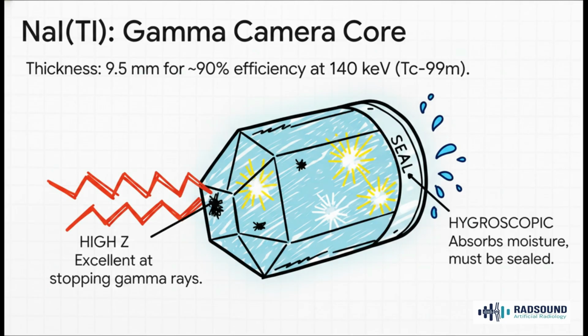And why is it so popular? Well, it has a high atomic number, that high Z, so it's really good at stopping gamma rays. It puts out a ton of light for each interaction, which gives us great energy resolution. And that standard 9.5 mm thickness is pretty much the perfect sweet spot for detecting the 140 keV photons from technetium-99m. Its one major downside, though, is that it's hygroscopic. It loves to suck water out of the air, which would ruin it, so it has to be perfectly sealed up.